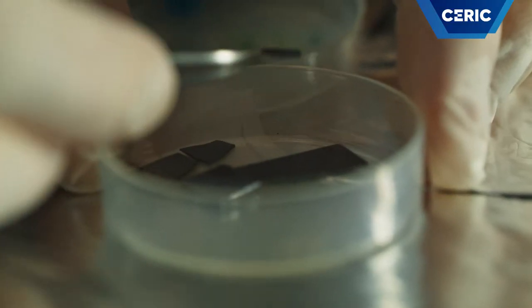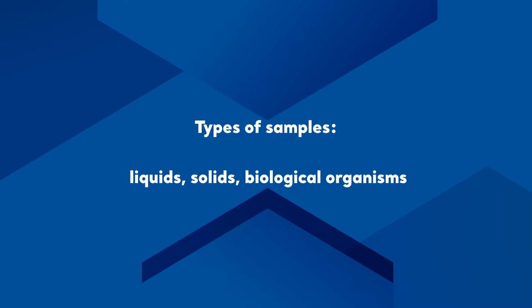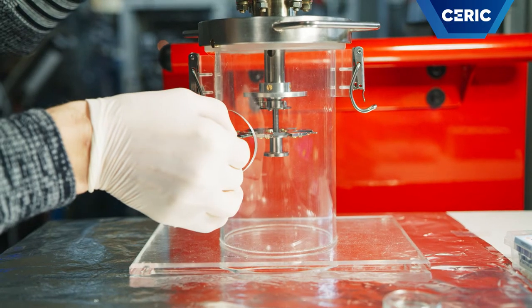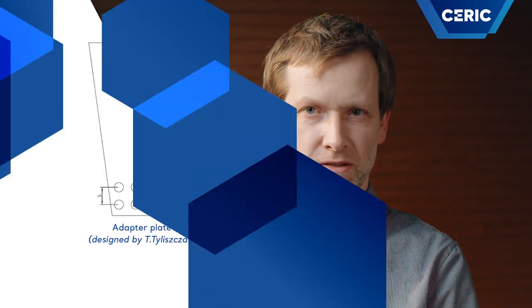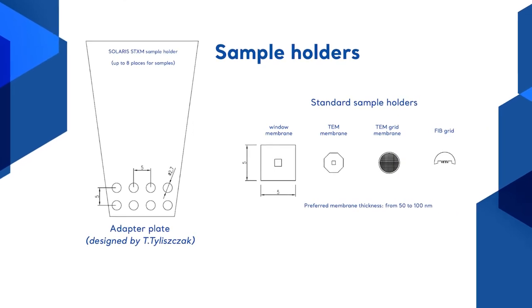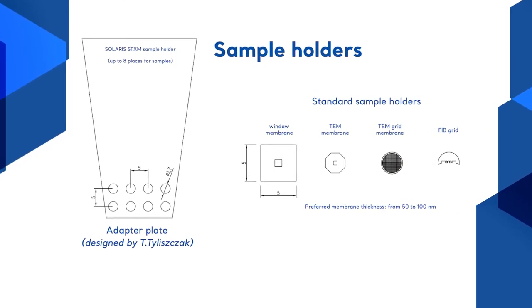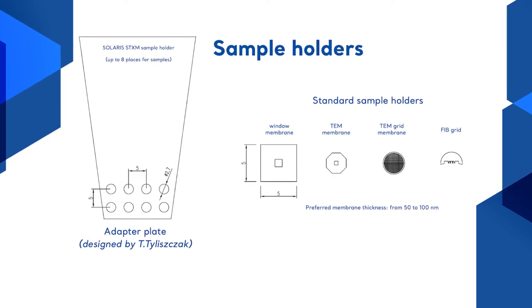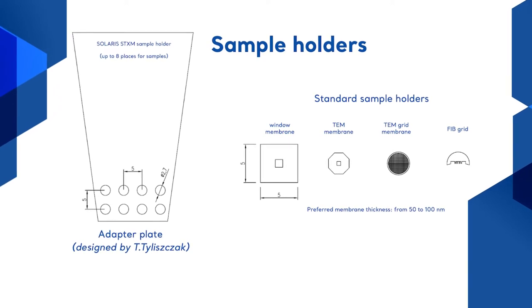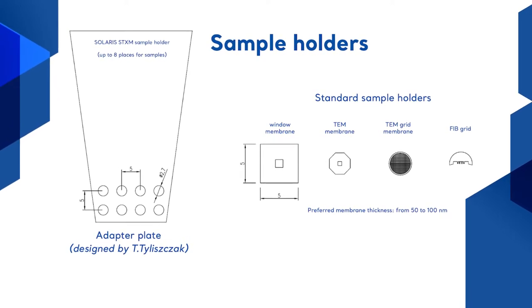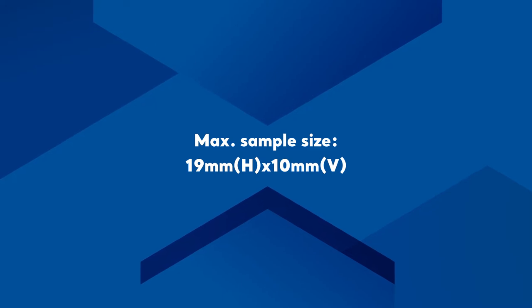A wide variety of samples can be tested in STXM: liquids, solids, biological organisms. The UHV standard is acceptable but not required. The sample should be sufficiently thin to allow minimum 5% transmission for X-rays in the required energy range. The standard frame size is 5 by 5 mm square or diameter equals 5 mm. Minimum frame size is 2.5 by 2.5 mm or diameter equals 3 mm. Maximum sample size is limited up to 19 mm by 10 mm.